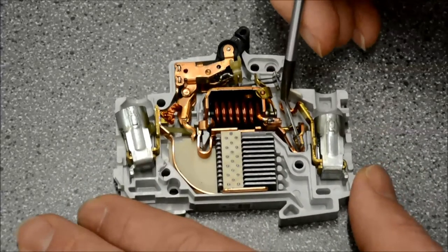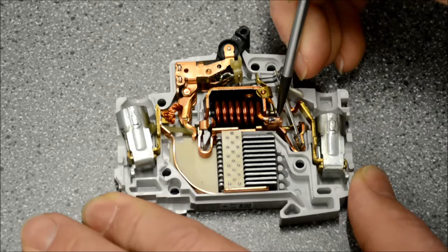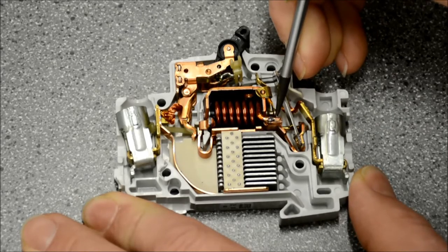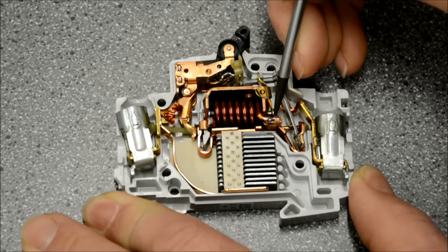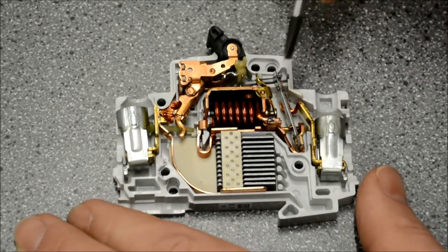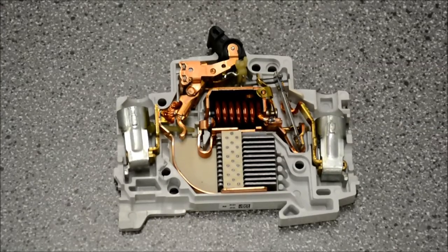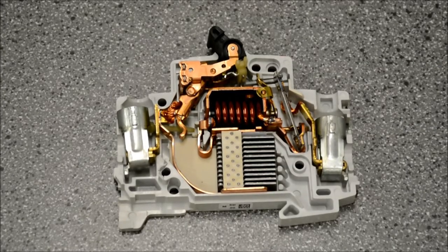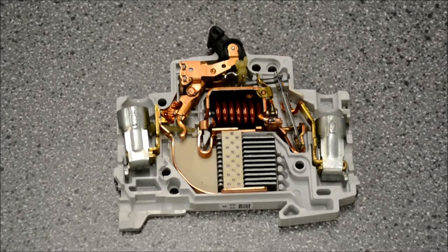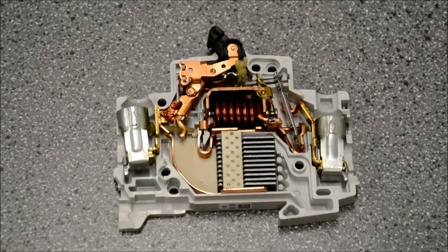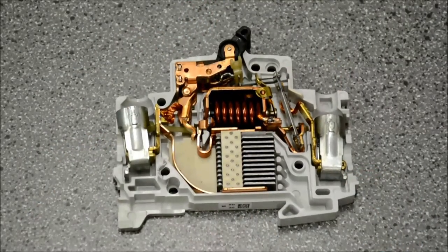If the current is sufficient to cause this plunger to move, it will activate this lever and activate the trip mechanism. We can effectively measure the strength of the magnetic field, and if you'll remember, the strength of the magnetic field is in direct relation to the amount of current flowing through the coil. In that manner, we can measure the amount of coil current that is available. So that is method number one to trip the circuit breaker.